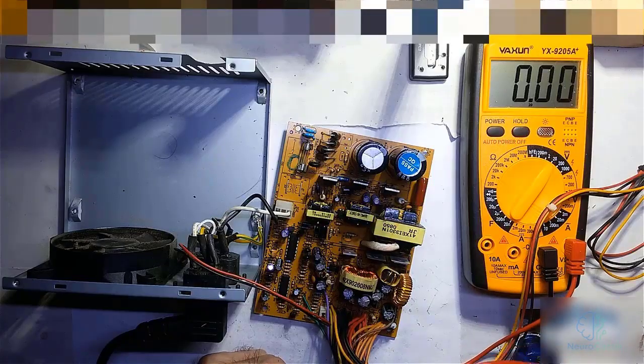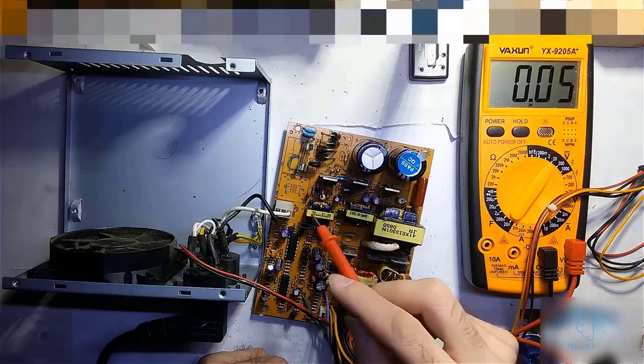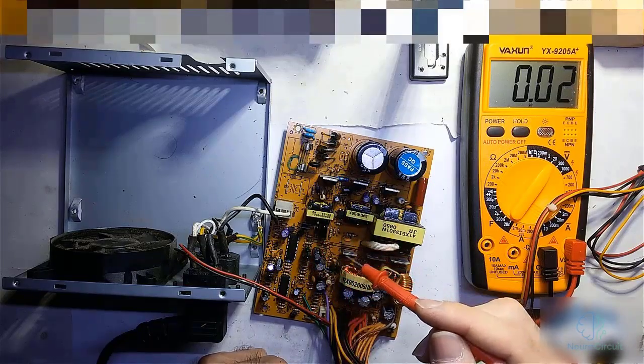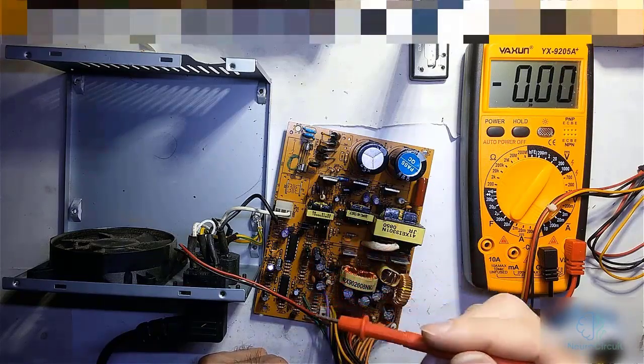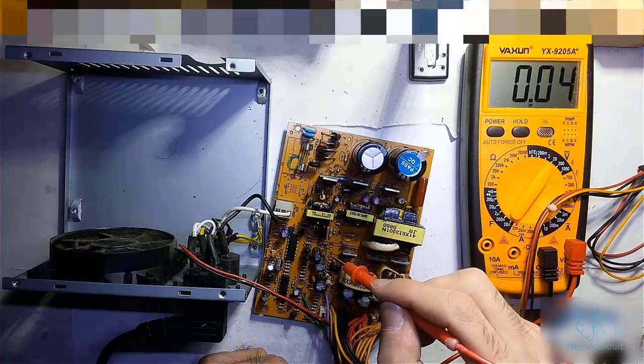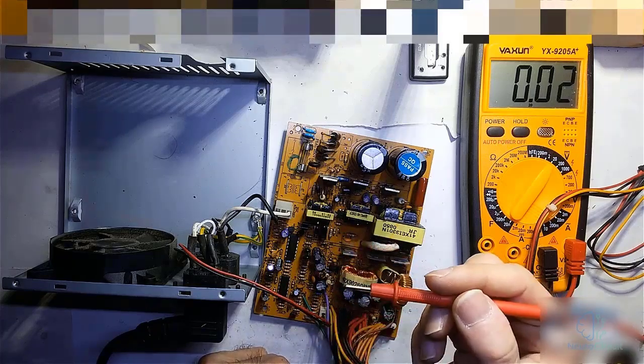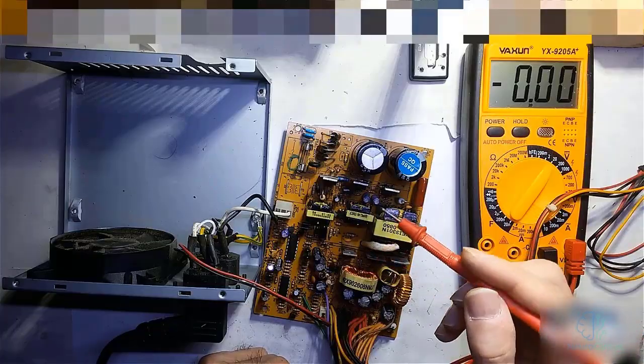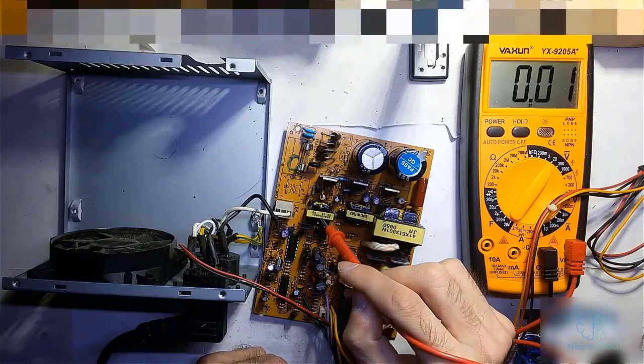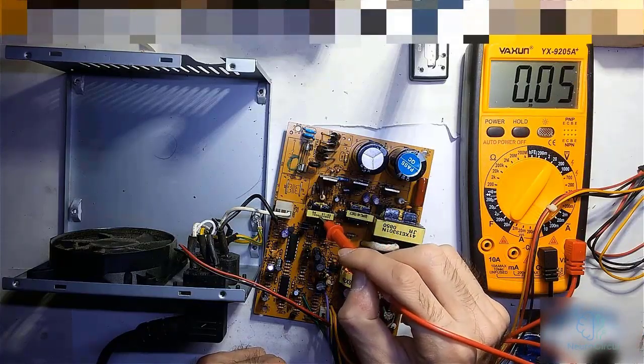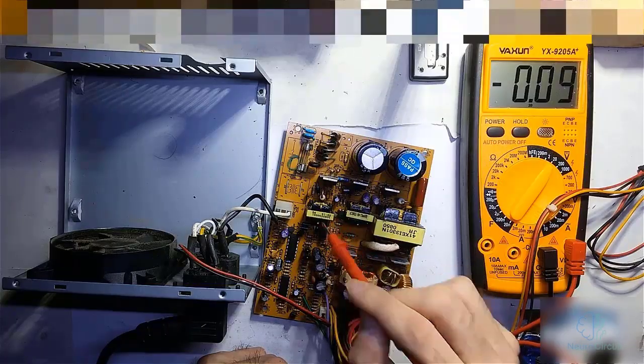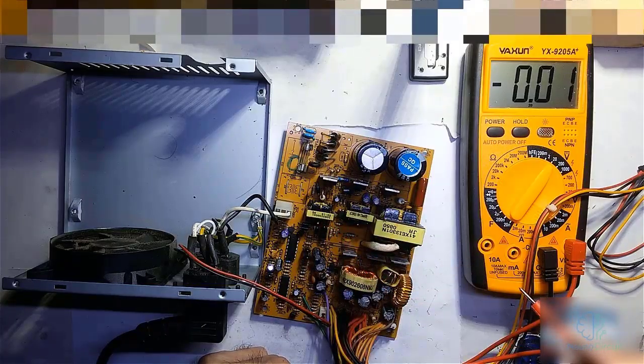There's a very crucial point I want to emphasize right now. If you have meticulously performed all the steps we outlined, replacing and testing every component with new ones, and yet you still find yourself without any standby voltage, then it definitely indicates that this specific transformer is defective. At that point, you should replace the current transformer with one that has the exact same part number written on its casing.